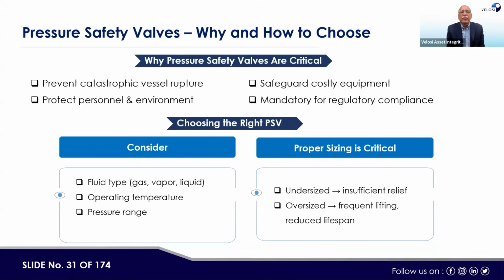Now, why are pressure safety valves critical? The problem is that if there is high pressure in an equipment or a highly pressurized system, it may burst. There could be an explosion, so they prevent catastrophic vessel rupture. They protect the environment and the people around, because an explosion or rupture can impact them. They also safeguard costly equipment, which should not fail or rupture. Then there is the mandatory requirement of API 520, API 521 or ASME Section 8. Choosing the right PSV, consider fluid type, gas, vapor, or liquid, operating temperature, and pressure range. Proper sizing is critical, because undersizing may lead to insufficient relief, while oversizing causes frequent lifting and reduced lifespan.